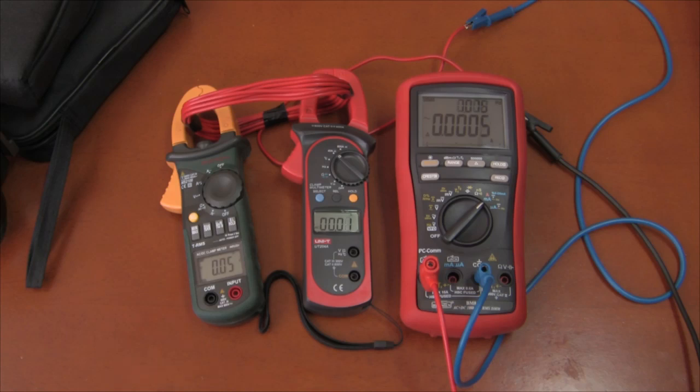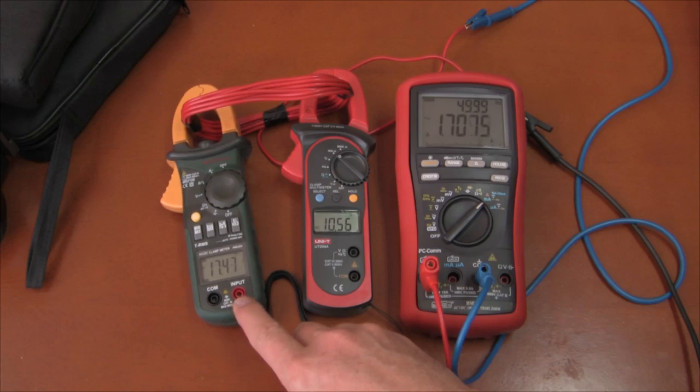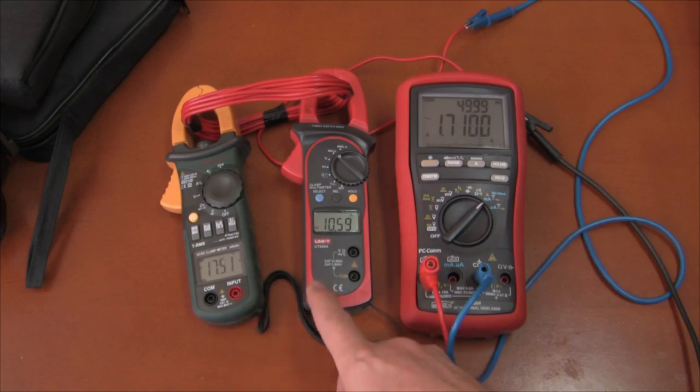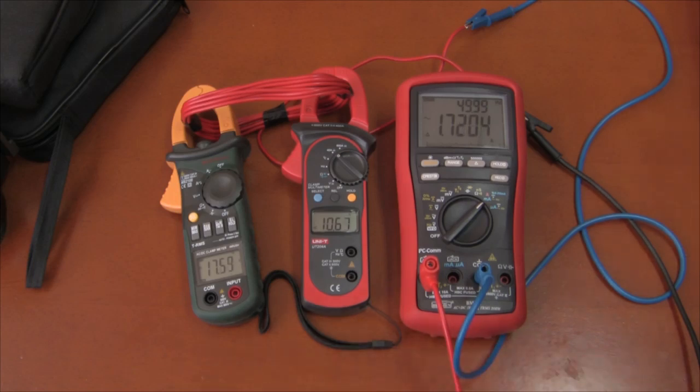Now we will turn on the heater and turn up the current to the heater, and you can see how the two different clamp meters respond in reference to the Brymen. This one should read 16.97, about 17 — you can see it's reading a little bit high. I believe that's just within its specifications. And this one is reading very low because it's reading the pulse width modulation and not getting a true RMS reading.